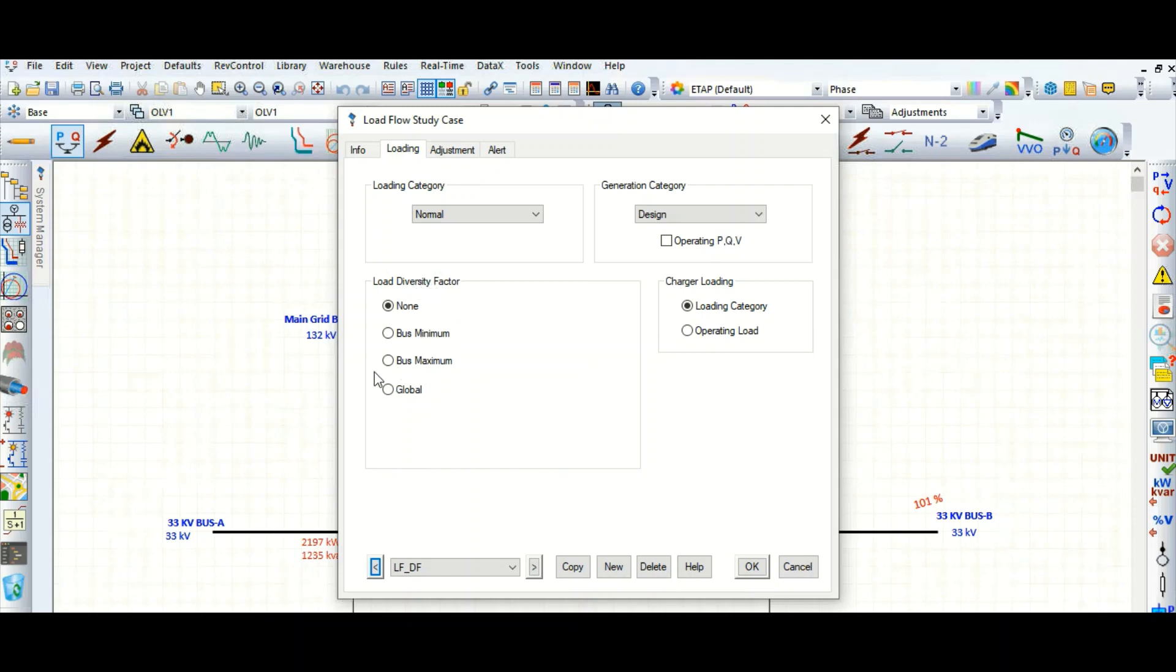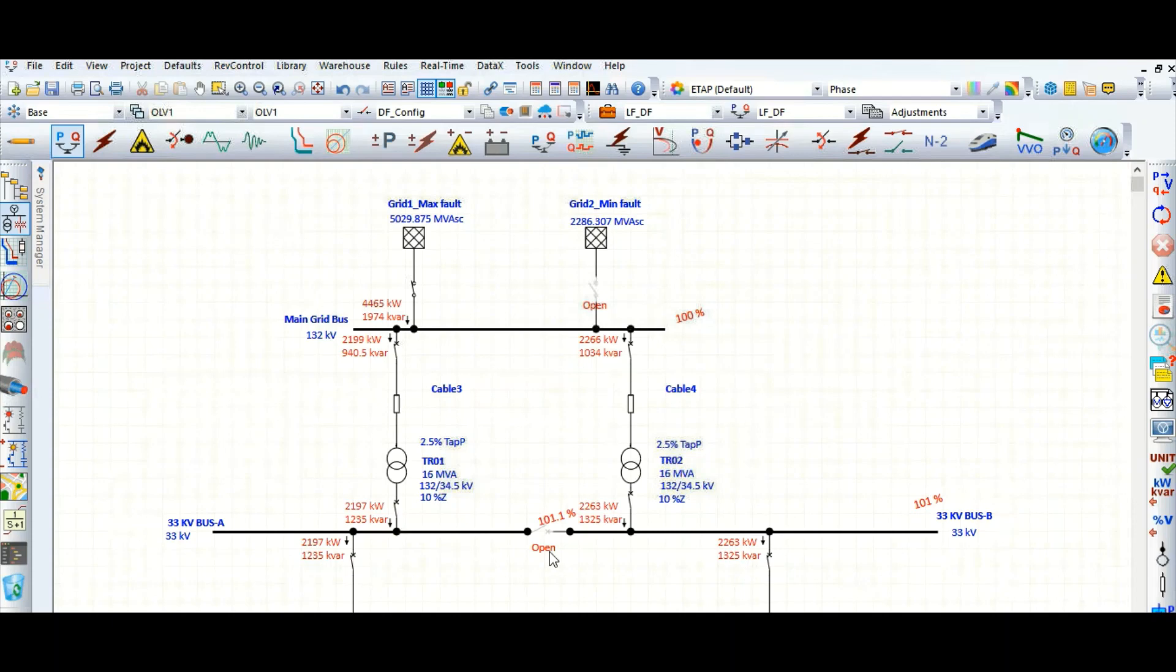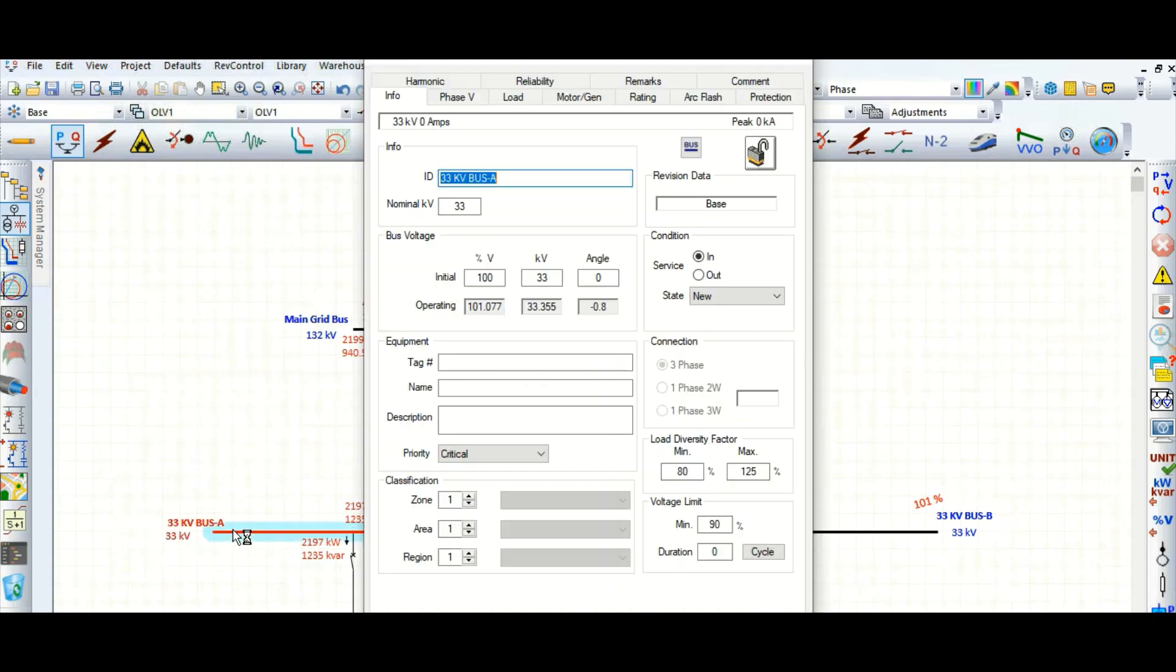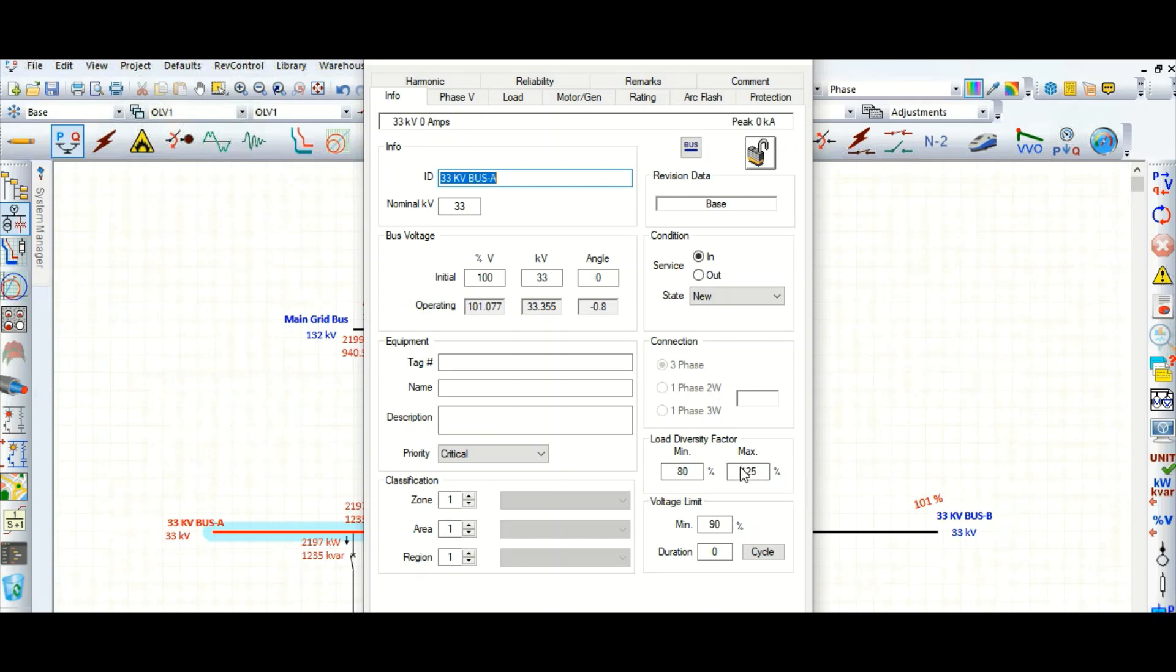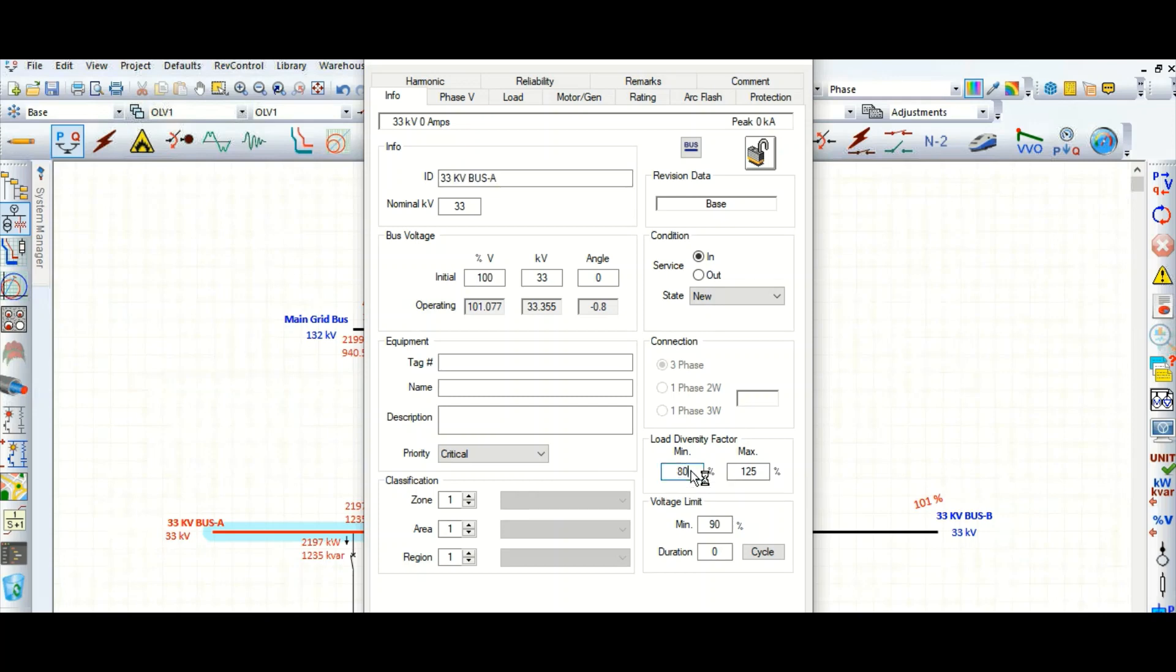If you set for the individual bus, the rating bus minimum or bus maximum rating, how to do that? Let's check. For 33 kV, if you go to the bus editor, here the load diversity factor: minimum 80 percent and maximum 125 percent. This is the default value. You can change it, for example, minimum 60 percent, maximum 80 percent or 100 percent.